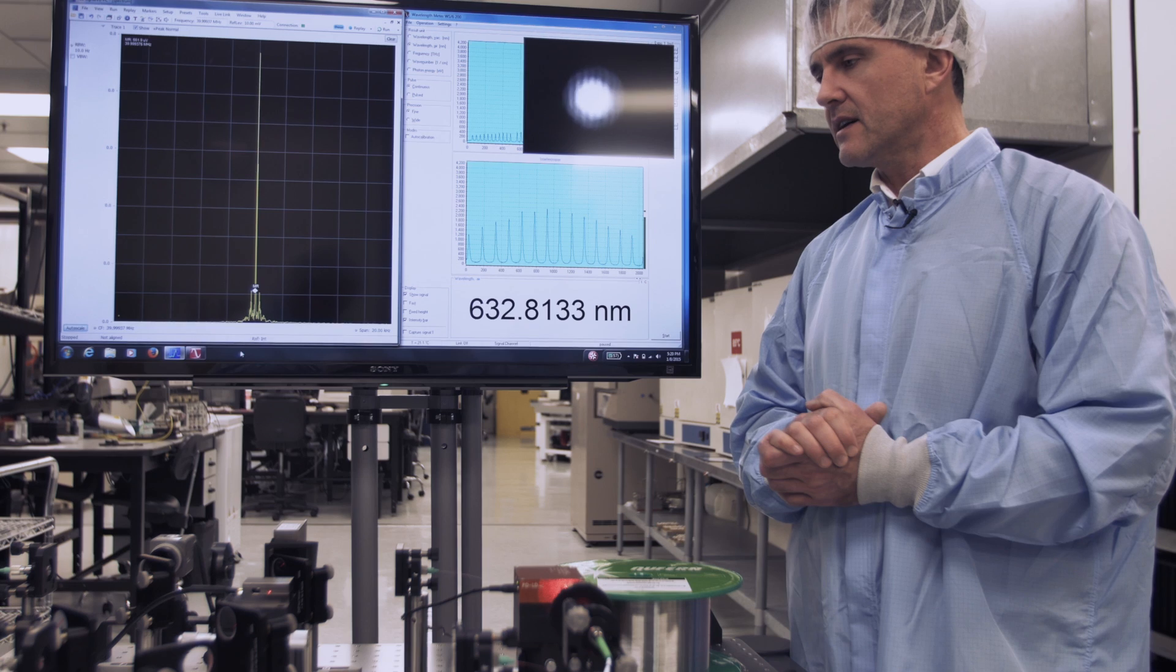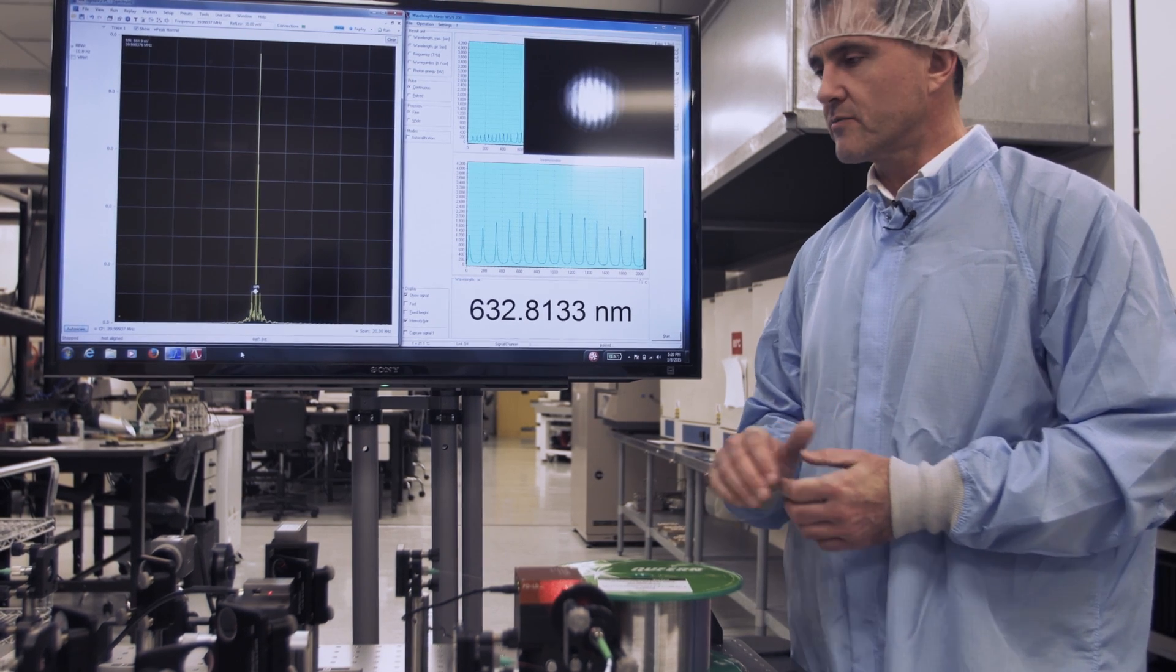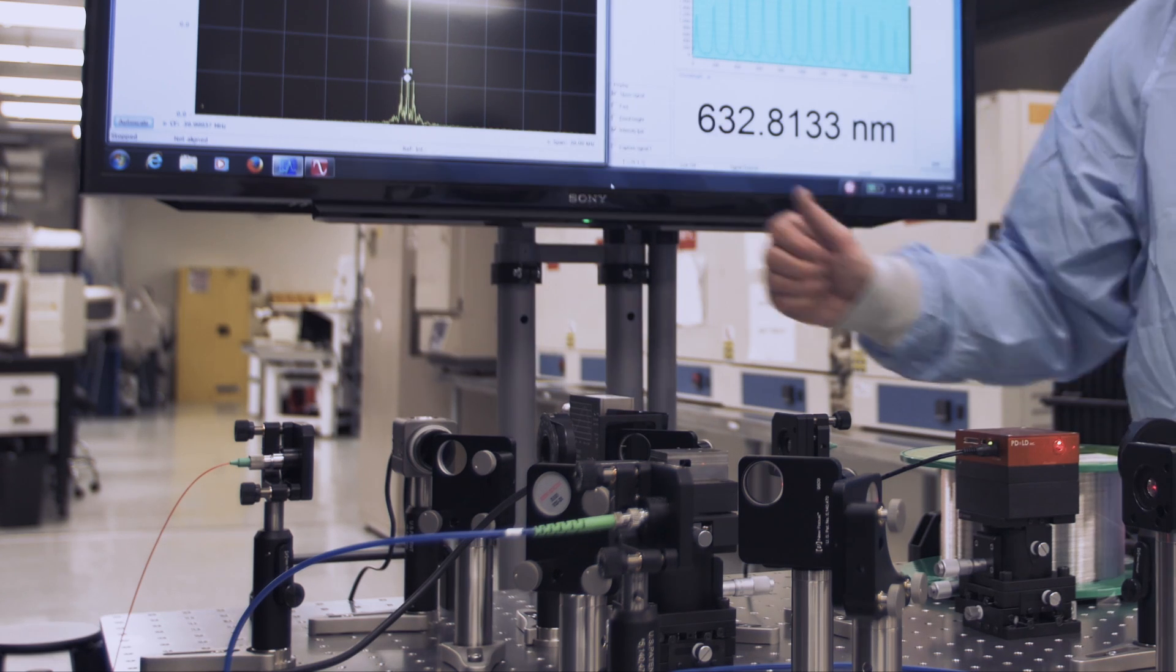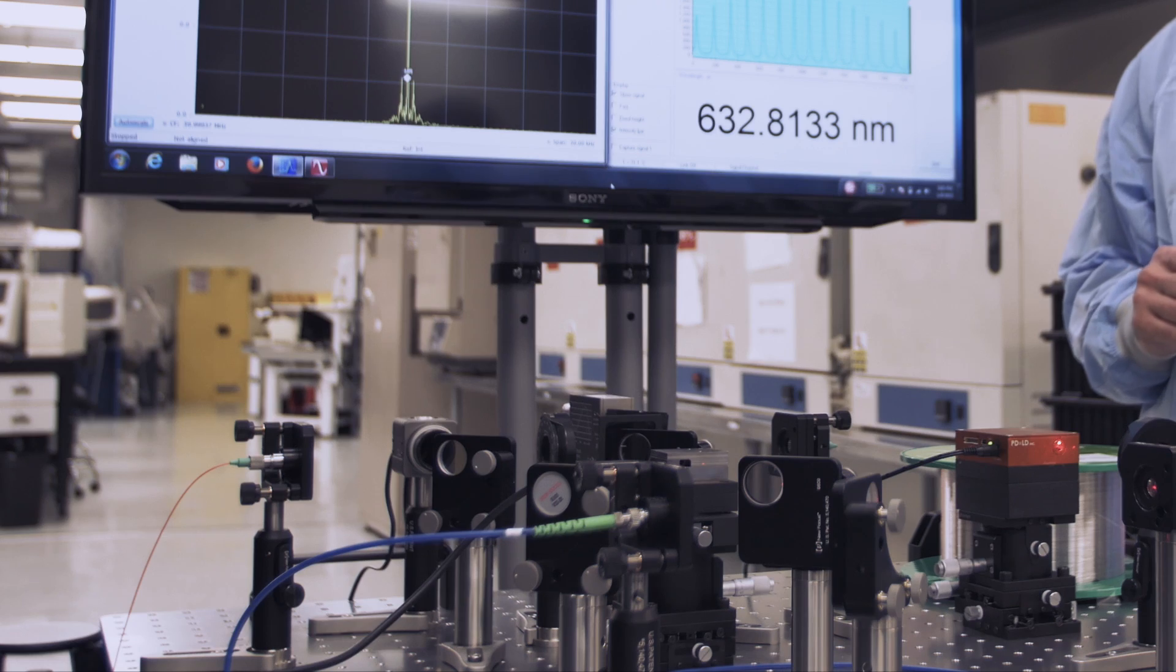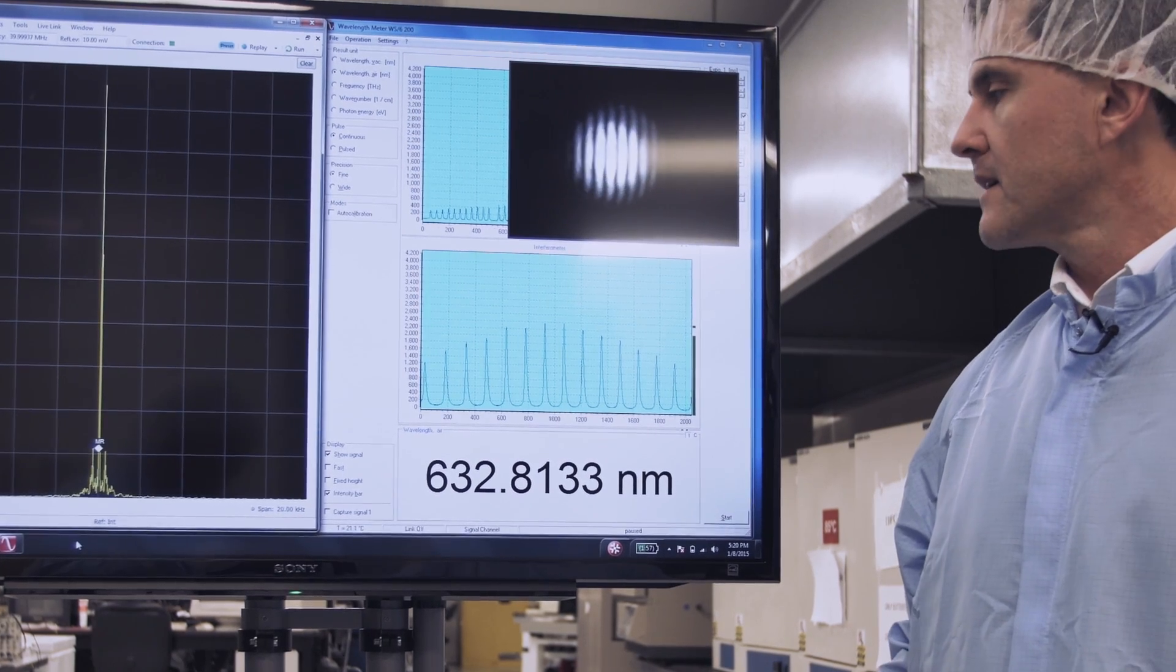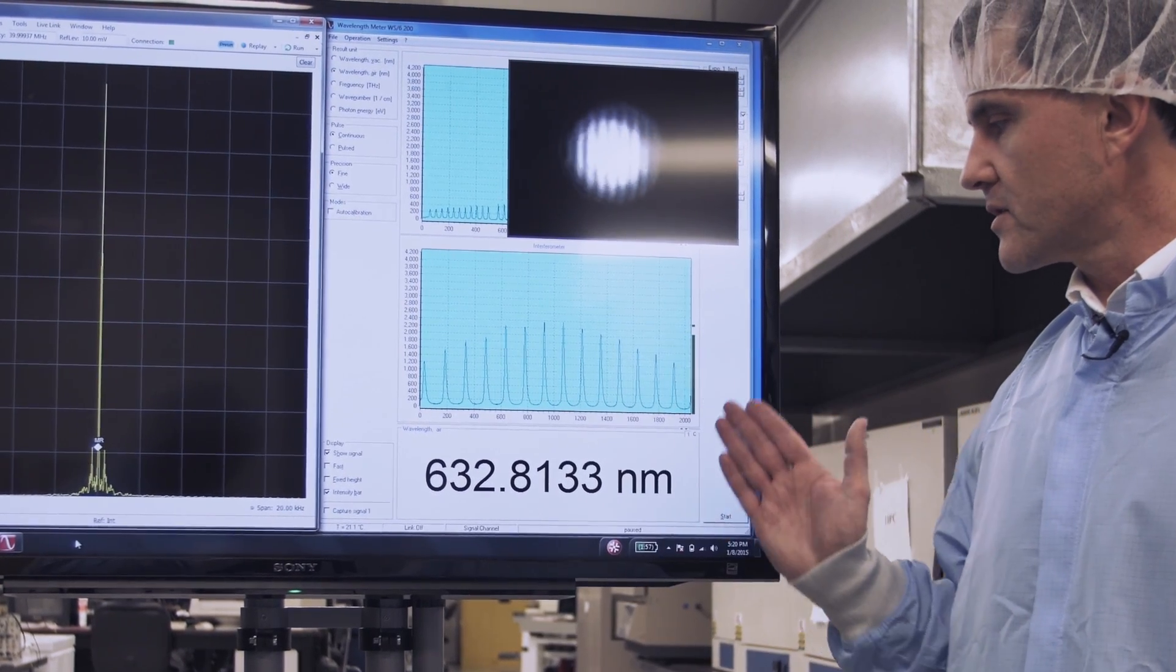Lastly, the absolute wavelength of the laser is measured by coupling into a single-mode fiber over here, and then feeding into a wavelength meter. The result of this measurement is shown in this window.